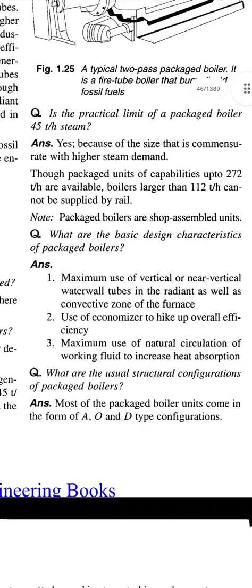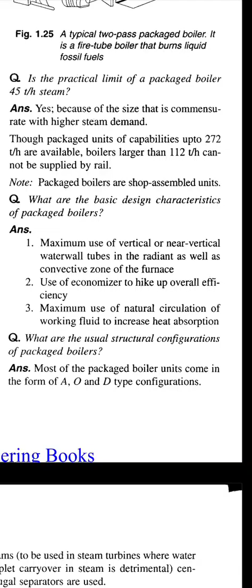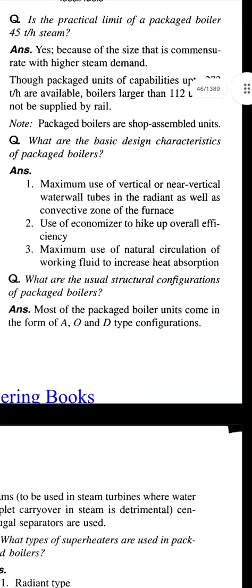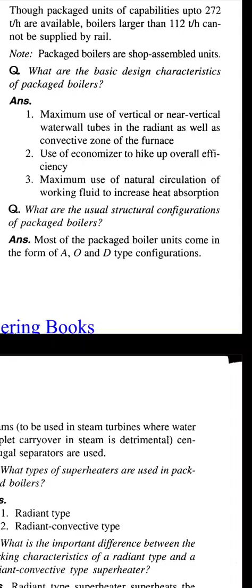Next question: what are the basic design characteristics of packaged boilers? Answer: maximum use of vertical or near vertical water wall tubes in the radiant as well as convective zone of the furnace. Use of economizer to hike up overall efficiency. Maximum use of natural circulation of working fluid to increase heat absorption. The question: what are the usual structural configurations of packaged boilers? Answer: most of the packaged boiler units come in the form of A, O, and D type configurations.